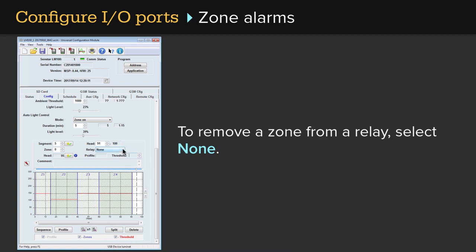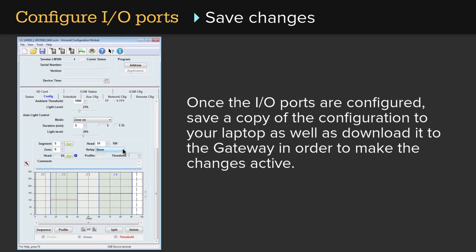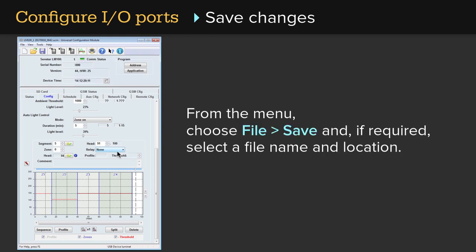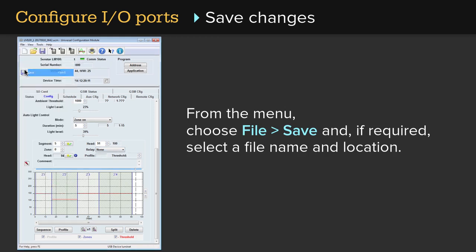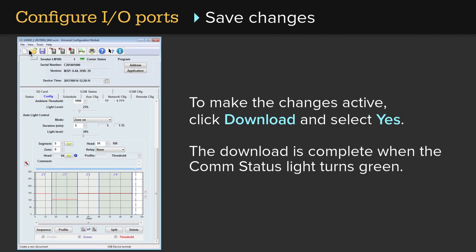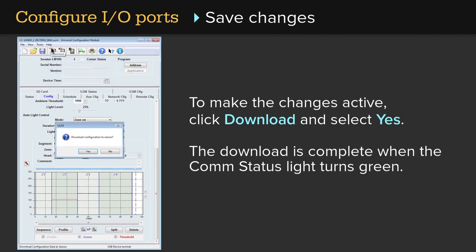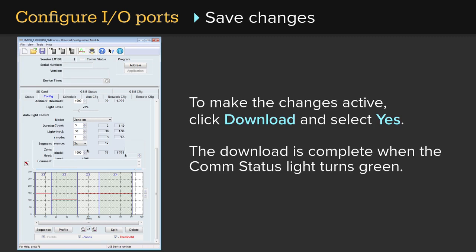Once the I/O ports are configured, save a copy of the configuration to your laptop as well as download it to the gateway in order to make the changes active. From the menu, choose File > Save and, if required, select a file name and location. To make the changes active, click Download and select Yes. The download is complete when the comm status light turns green.